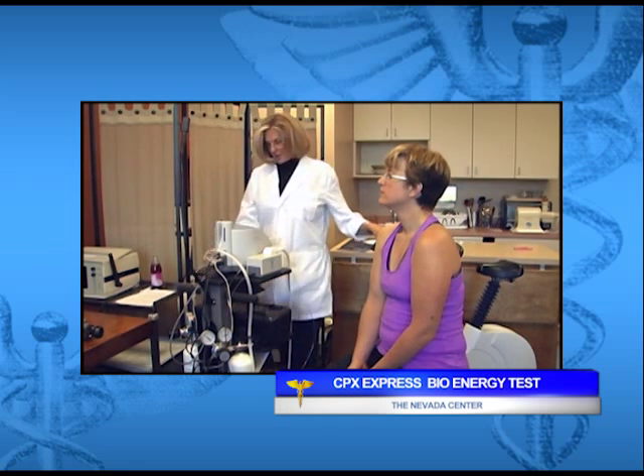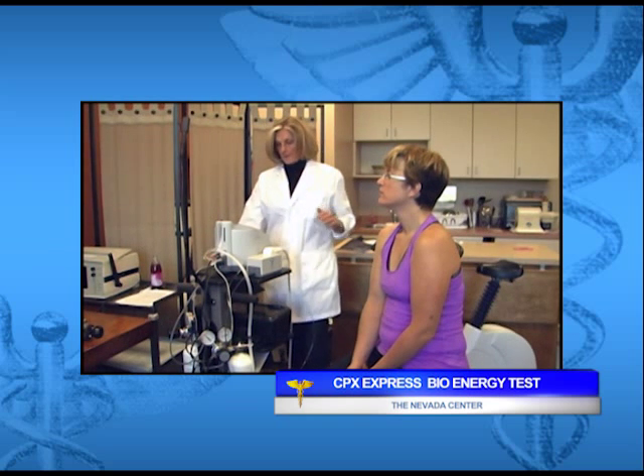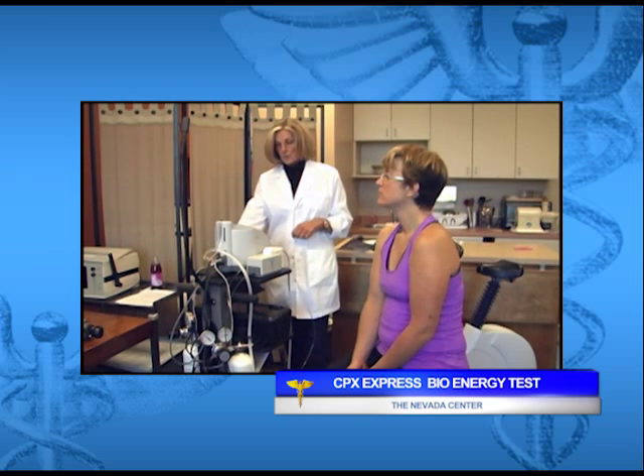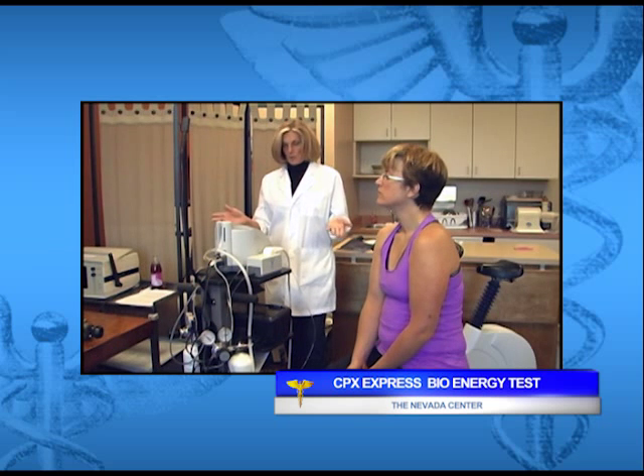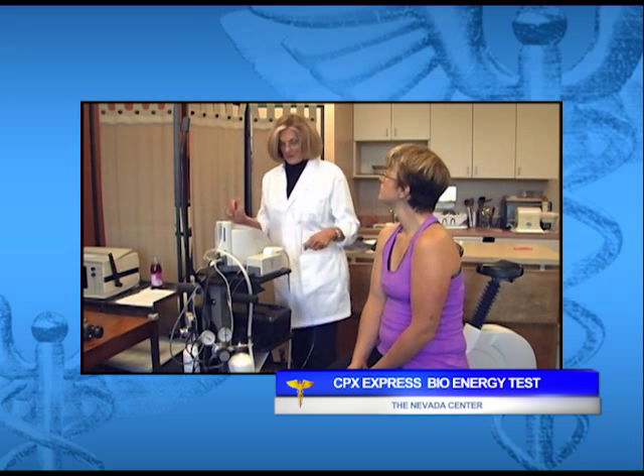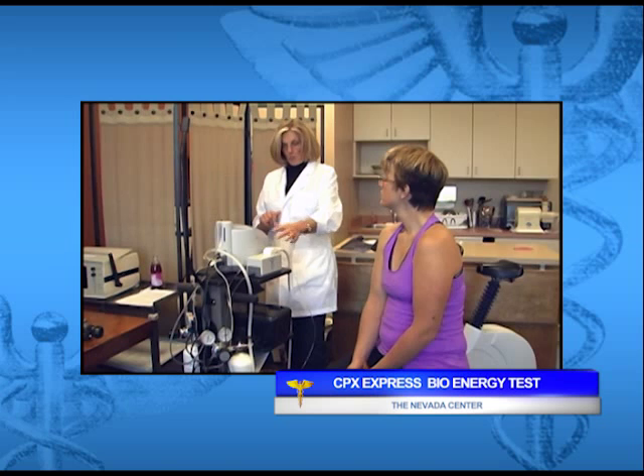So once the tanks are open, you're going to hit the little VO2 icon, and it's performing AutoCal. This takes a few minutes. You can hear the tanks kind of buzzing. And what we're doing is AutoCaling everything here.